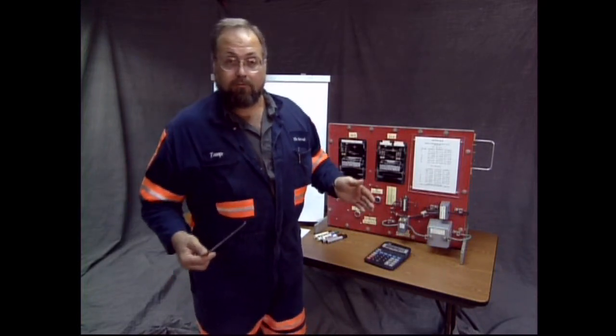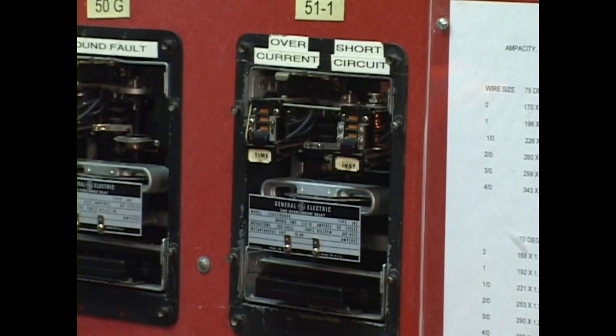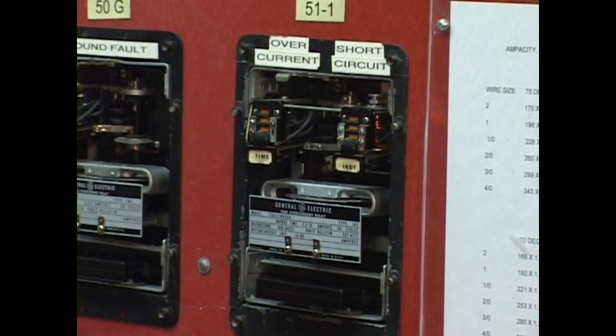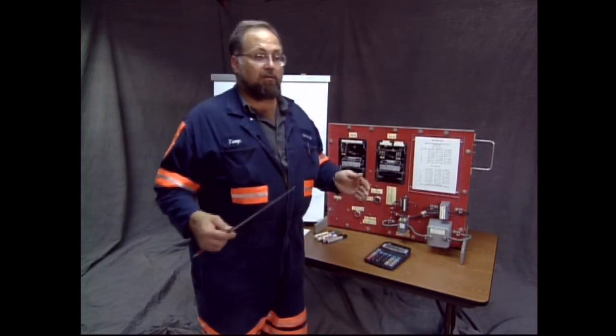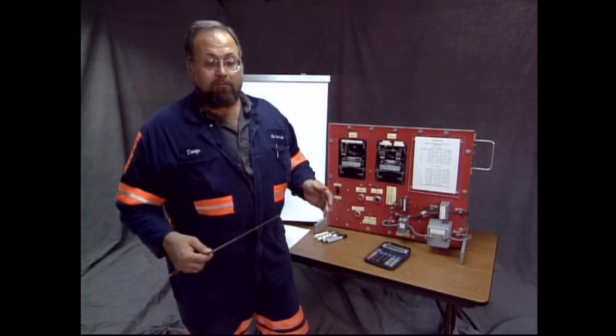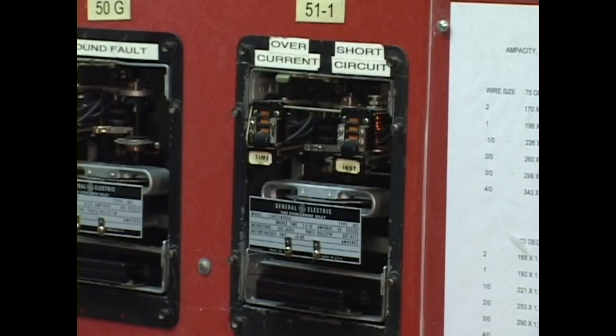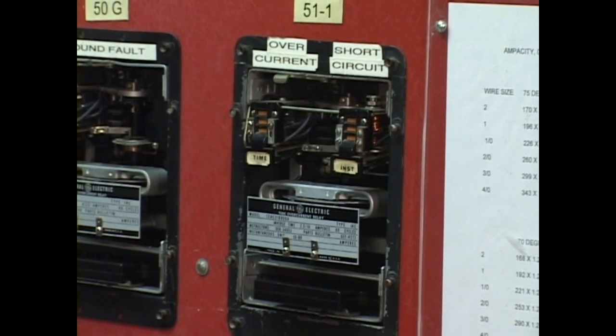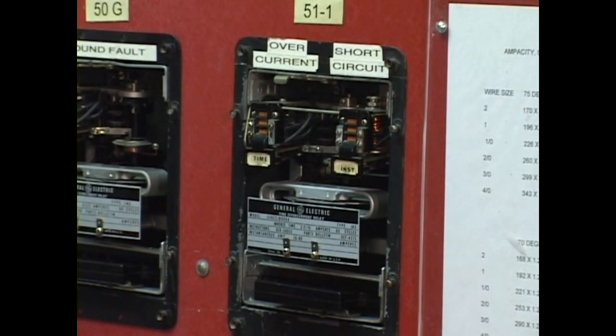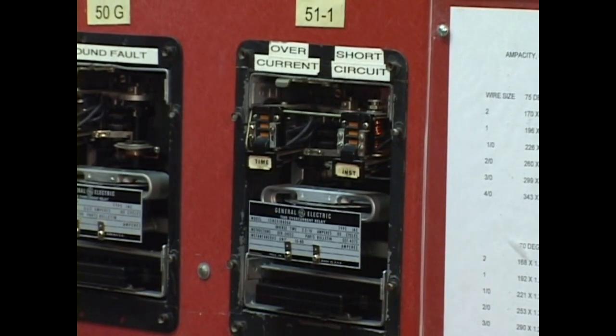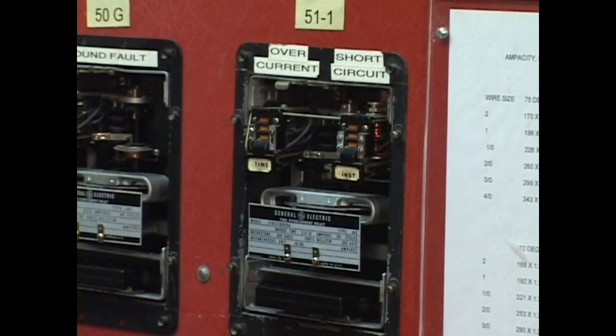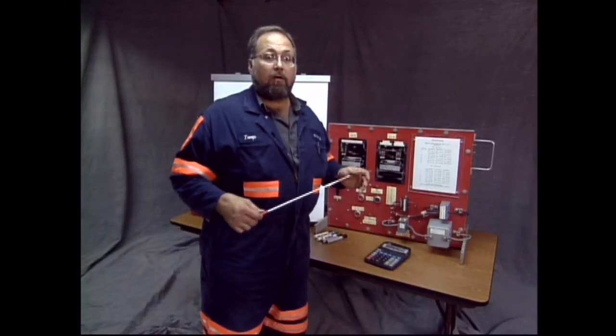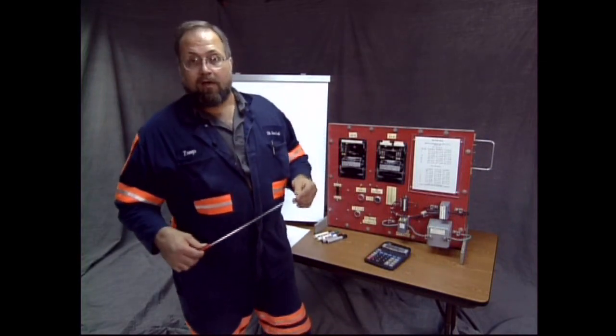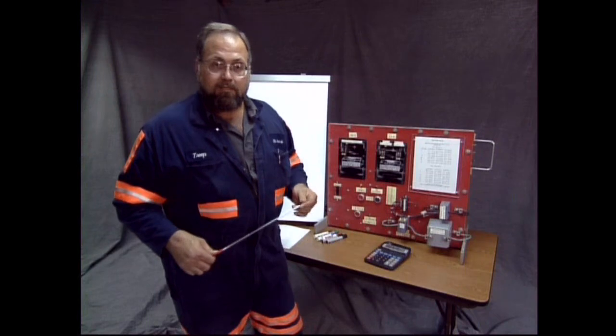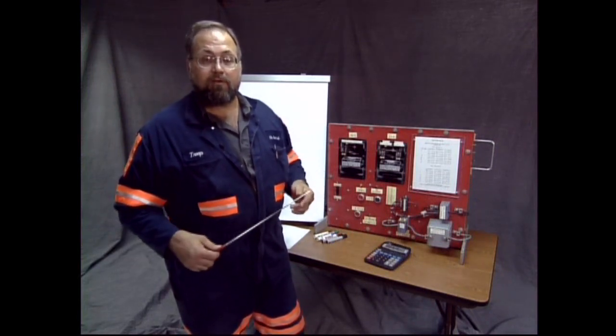They're both too many amps. There's too many amps for the conductor. An overcurrent is 125% of the ampacity of the cable. A short circuit can be a maximum of 600% of the ampacity of the cable. So they're both too many amps. The main difference between the two is the magnitude and the duration of the event. With an overcurrent, it could be a lengthy time. You could possibly time this thing with a chronograph, with a watch. But with a short circuit, we're talking instantaneous. It's so fast as to virtually be no delay. It's in a fraction of a second. And there's not enough time involved to cause damage to the CTs or the wiring. You're going to interrupt this event quickly.